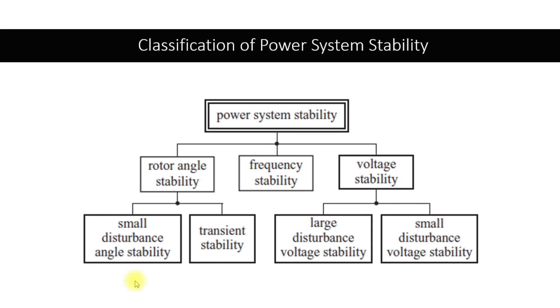Voltage stability is also of two types. In large disturbance voltage stability, the power system is subjected to a very strong disturbance, such as a three-phase fault or a single line-to-ground fault. Small disturbance voltage stability is where the system is subjected to a small variation in voltage, for example due to starting of a motor, tripping of load, or addition of a large load at the same time.